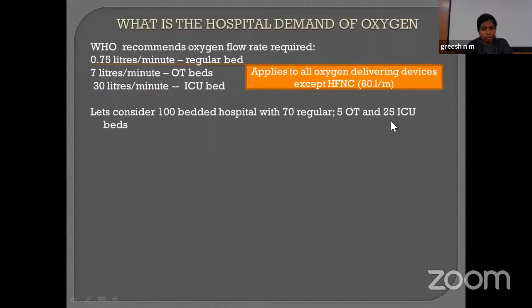So now let us calculate the oxygen demand of a 100-bedded hospital, which has 70 regular beds, 5 OT beds, and 25 ICU beds. The oxygen requirement in this hospital is the number of regular beds times the flow rate, plus the number of OT beds times the flow rate, plus the number of ICU beds times the flow rate. Substituting the values, we get the oxygen demand of the hospital in liters per minute. If we multiply by 60, we get the oxygen requirement in liters per hour. So for this 100-bedded hospital, the requirement is around 50,250 liters per hour.